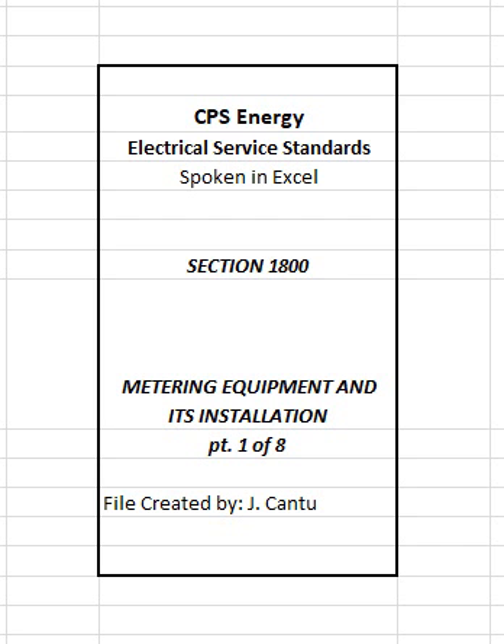2. Line and load conductors and connections. All meter sockets must have the line side, source, conductors connected to their top terminals. Load side conductors must connect to the bottom terminals of the meter socket. Refer to Figures 1803 through 1809 for proper conductor terminations in standard, single position, self-contained meter sockets. Exception. Photovoltaic, PV, meter sockets shall have conductors from the solar installation side connected to the top terminals as the solar production becomes the source. The PV meter is a non-billing relevant meter.